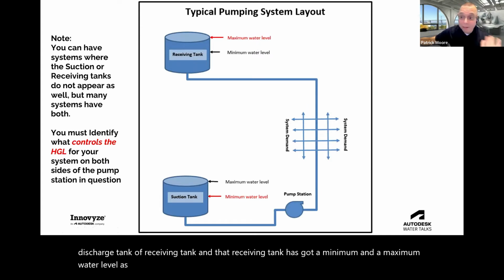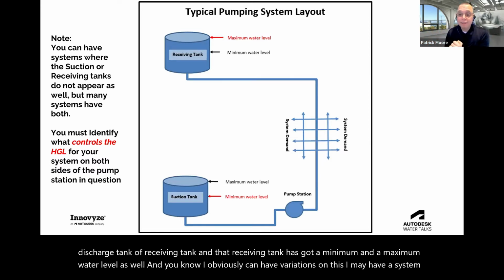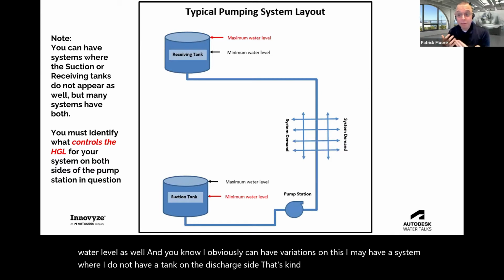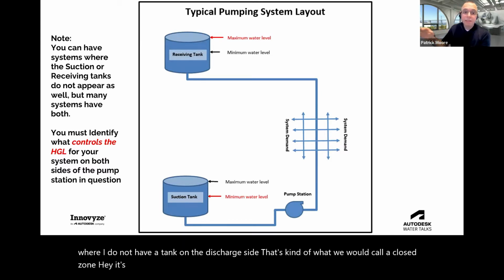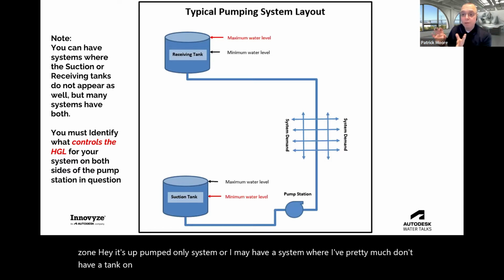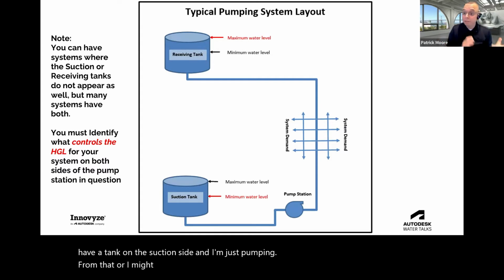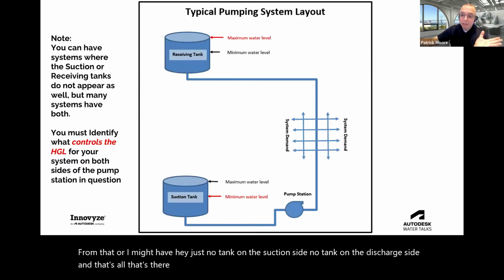And I obviously can have variations on this. I may have a system where I do not have a tank on the discharge side. That's kind of what we would call a closed zone. It's a pumped only system. Or I may have a system where I pretty much don't have a tank on the suction side and I'm just pumping from that. Or I might have no tank on the suction side, no tank on the discharge side, and that's all that's there. But something is controlling the hydraulic grade line, so understanding your system.